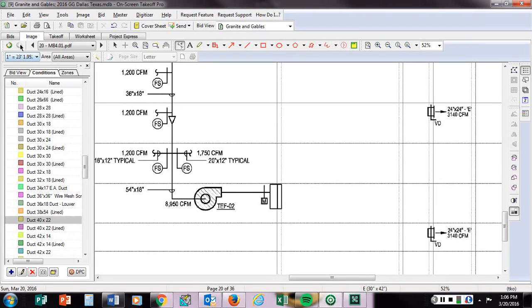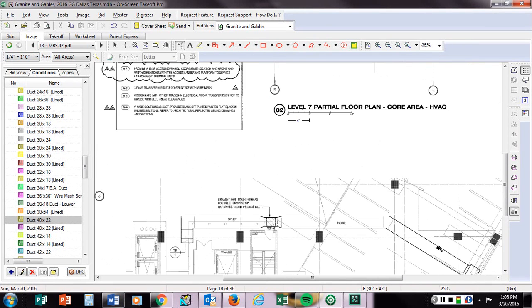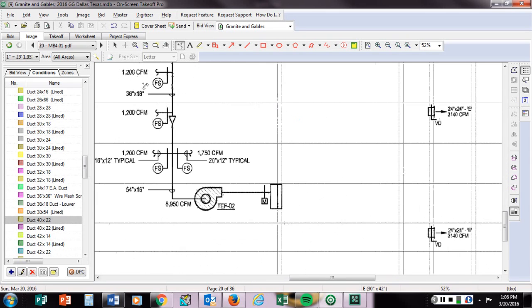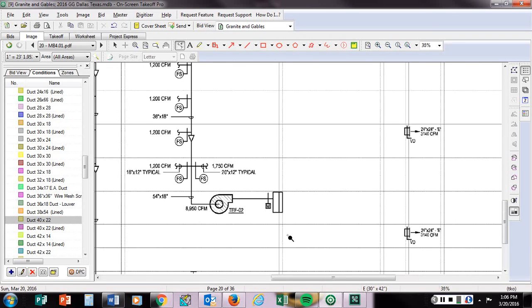Now I'm going to go back to that other print. You can see this is actually where the fan is, and this is the exhaust duct coming off of that. So anything going horizontal, we want to do on these plan view drawings, not the riser diagram — we use the riser diagram just to grab the duct that's going vertically. Hopefully that makes sense.